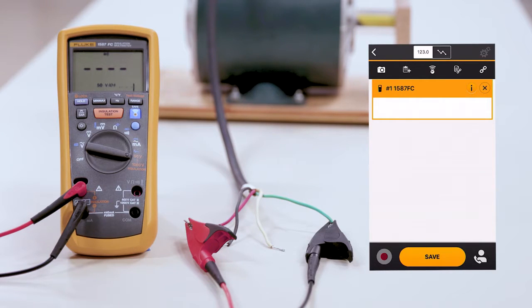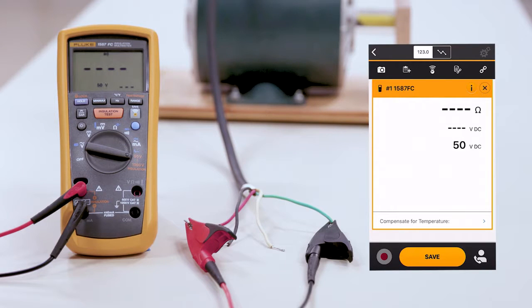Typically in an insulation test, we want to double the voltage rating. In this case, this motor is a 480-volt motor. We're going to change the range of our insulation meter to 1000 volts. To do that, you'll hit the Range button.